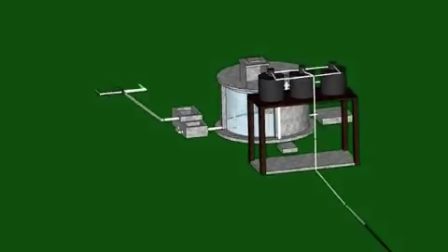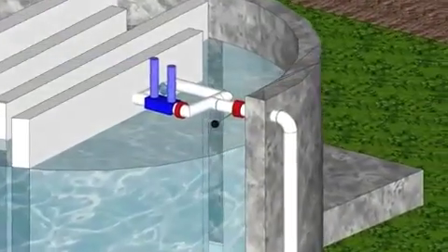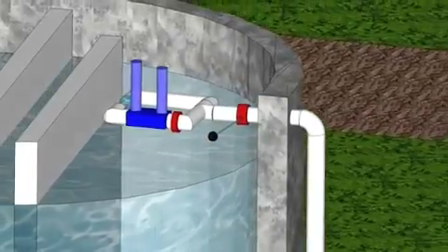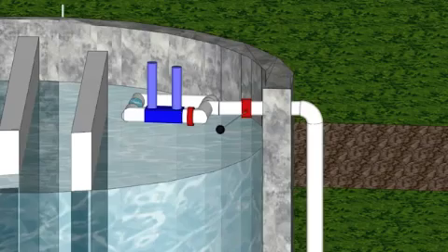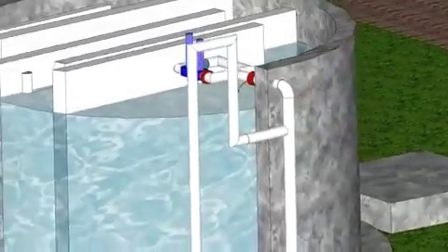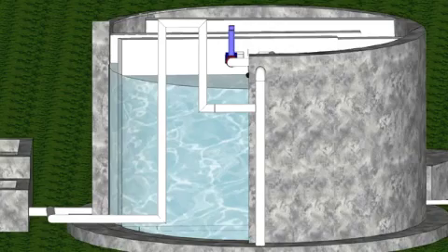The disinfection process will take place prior to the water entering the distribution tank. The application of chlorine to the system will eliminate the microorganisms, disinfecting the water. Engineers Without Borders proposes to add 2 separate calcium hypochlorite tablet feeders in the remaining chlorine drip system housing. The feeders will provide a convenient and practical approach to the chlorination process while being able to handle the peak water demand of the village.